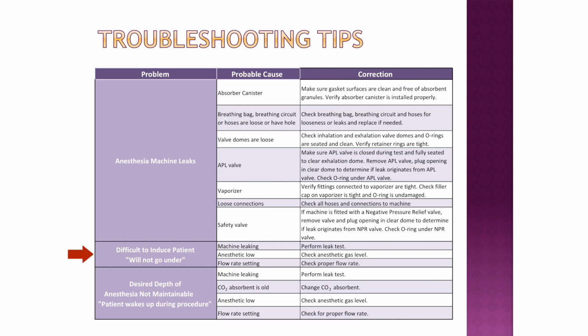Patient won't go under? Again, do a leak test, make sure you've got gas in your machine, make sure your oxygen is on, and you've got proper flows. And if the patient wakes up during the procedure, again, check for leaks. Make sure your soda sorb is not old or expired. Make sure you've got gas in your machine, and make sure you've got your proper flow rates.